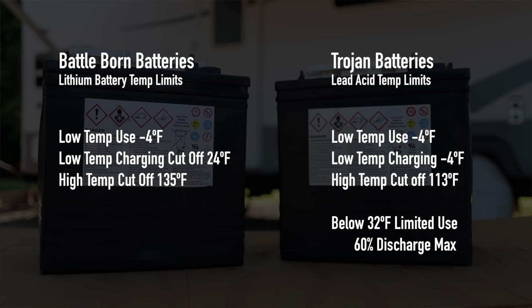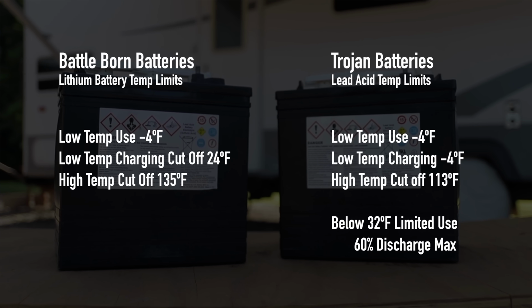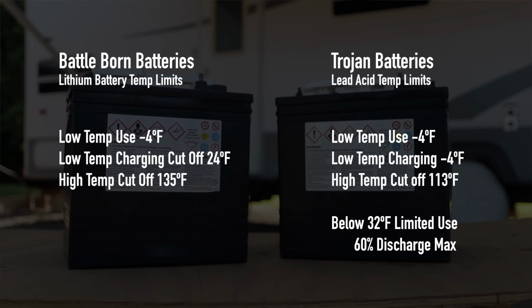But some people might be surprised that they don't want you to bring it past 60% depth of discharge. Usually with a lead acid battery, you think about bringing it safely to 50% and charging it back up, and you're not shortening the life of the battery. But if it's below 32 degrees, they don't want you to take it below 60% of that battery. So you can't use the full capacity on a lead acid battery. That's because if you have a depleted lead acid battery in freezing temperatures, that battery can freeze. And once that battery freezes, it's no longer usable. It's done. The battery will be dead. So each battery type has its own limitations, and knowing them is good. But the BMS device in a lithium battery will help protect it in those extreme environments.